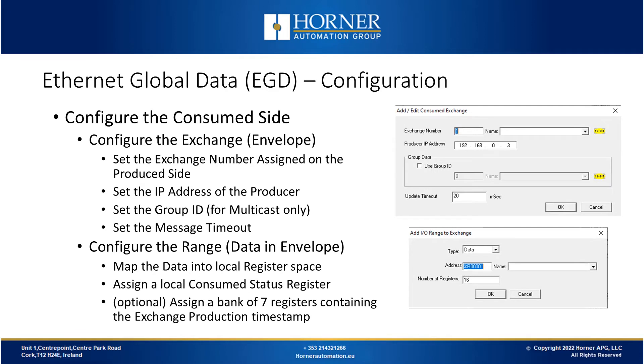Next we have to configure the consumed side of the exchange. First we must set the exchange number to match the exchange number that was assigned on the produced side. We also have to set the IP address of the producer. If it's a multicast type message to a group we also have to set the group ID matching the one on the produce side. Then we assign a message timeout — this is not the same number of milliseconds that was assigned on the produce side. Then we must configure what we'll do with the data that comes in, moving it into our local register space of the consuming OCS. It doesn't have to be the same register numbers as on the produced side. Next we'll assign a status register so we can tell if communications are working properly. And optionally you can also map in the timestamp of when that message was transmitted into a local variable.